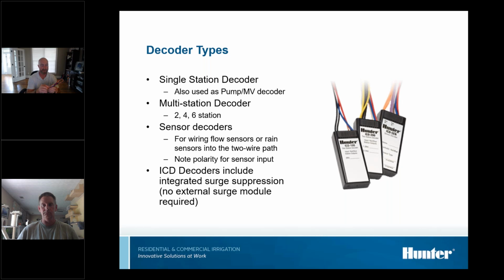You want to pay attention to the positive and negative leads on these. On your sensor, you typically will have a black and a red lead, so you want to wire your red to the positive and your black to the negative. We talked about how ICDs include that integrated surge suppression, so you don't have to buy an extra surge suppression module when grounding.